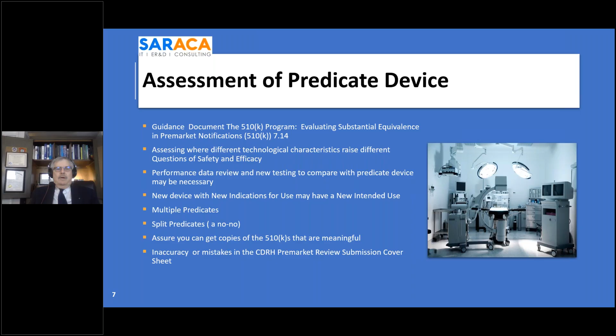This is particularly true when you have, say, marketing putting together a sales sheet that is included in the 510K. And it has either new indications that were not in the original 510K or the indications for use vary slightly. So you want to make sure that it's consistent all the way through. Now, there are small inaccuracies, and unfortunately, I made an error in not insisting that this be a full-size document, but this is one of the most important documents in your submission other than your summaries.